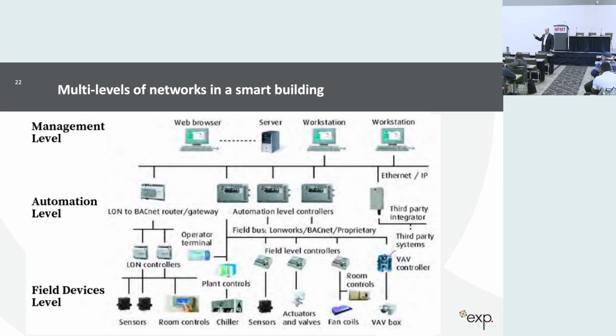The key here is you want to make sure that whatever your end device is will still operate if you lose the network. That's key, because the automation level controls all those end devices, but you want to make sure there are some processes in the end devices to keep things running.